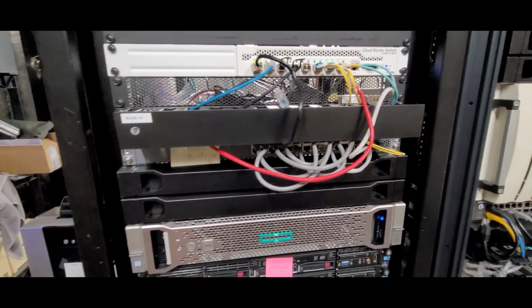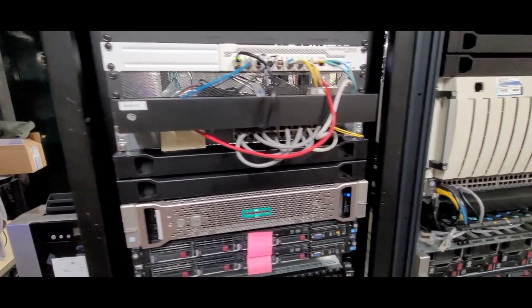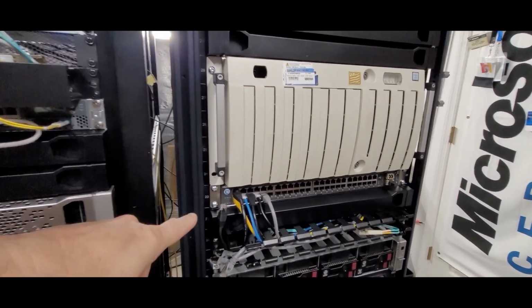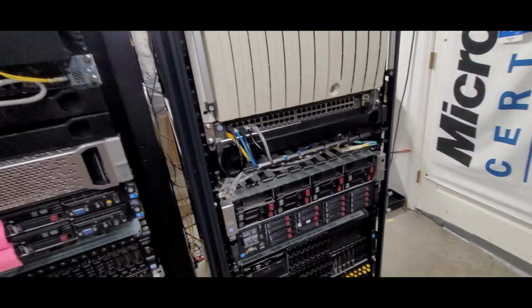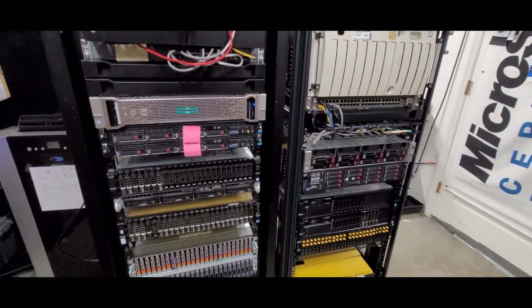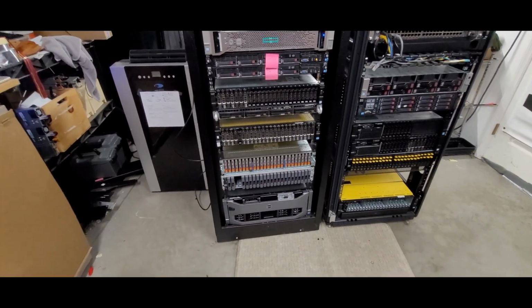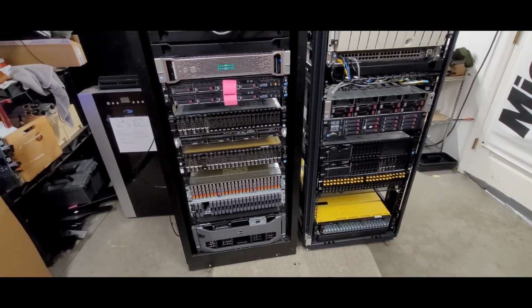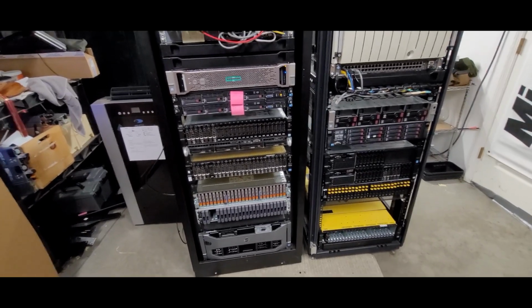Those are a little hotter, and they have to have fans, so they're not passive, they're active. So by understanding the nature of your switches and their heat output, and the servers and the disk arrays and your heavy hitters like your quad arrays down here, you can come up pretty quickly with a very clear picture of exactly how much heat is going to be produced.